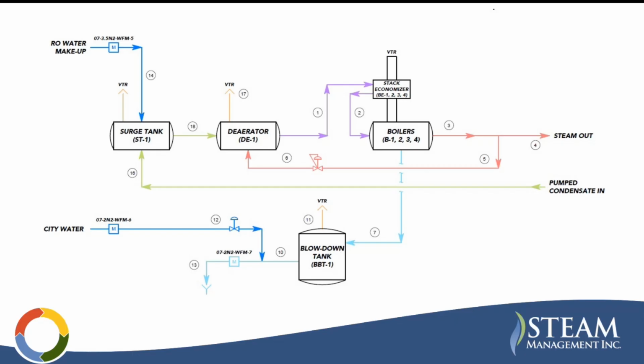That is heated to deaerate the water. So there's a steam consumption here. And then the deaerator will feed. From here, you're going to call this feed water typically, and you're going to feed the boilers with that, and they're going to generate steam again. What we're concerned with is this other stream here, which is the blowdown, and that is a stream coming off of the boilers to remove impurities, and we'll talk more about that as we go.